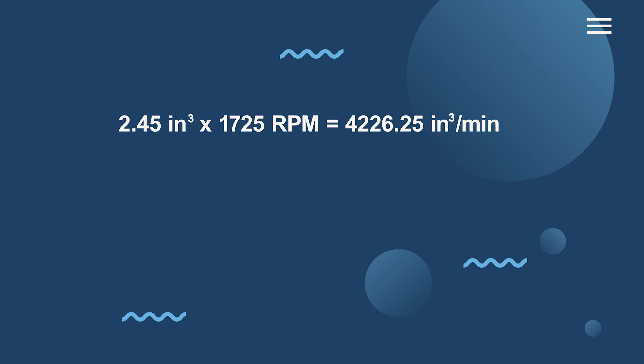Typically, speed in this context is measured in revolutions per minute, or RPMs. As an example, let's say we have a pump with a displacement of 2.45 cubic inches per revolution, and it's running at a speed of 1,725 revolutions per minute. The flow rate would be 2.45 times 1,725, which equals 4,226.25 cubic inches per minute of flow.